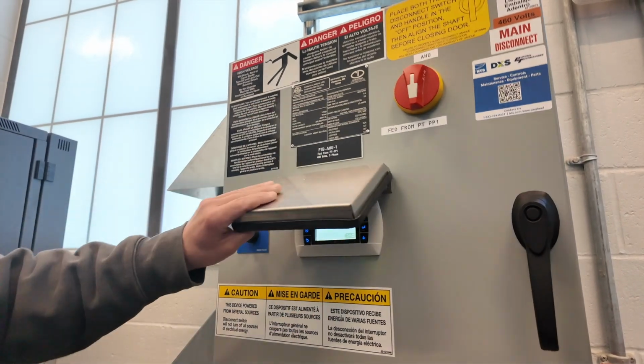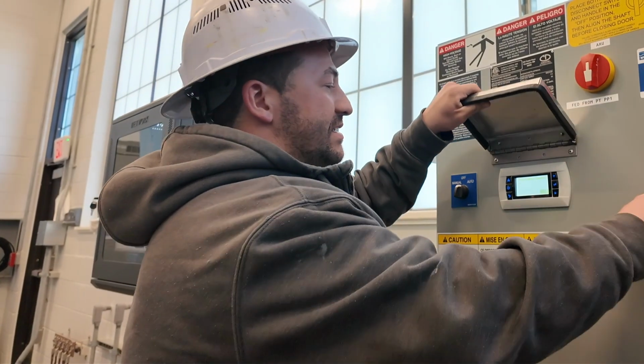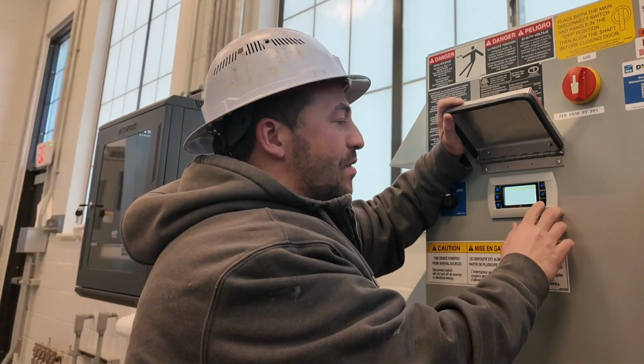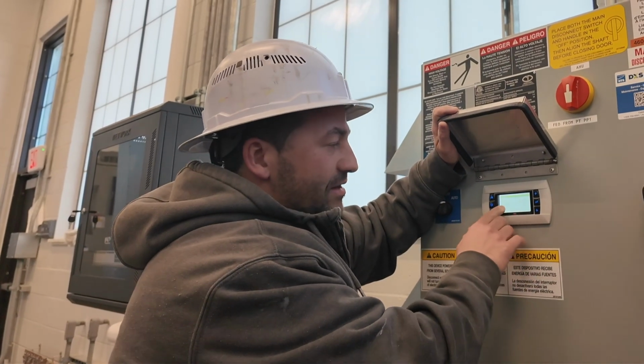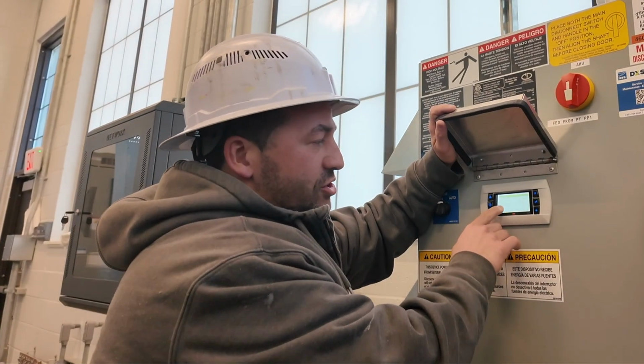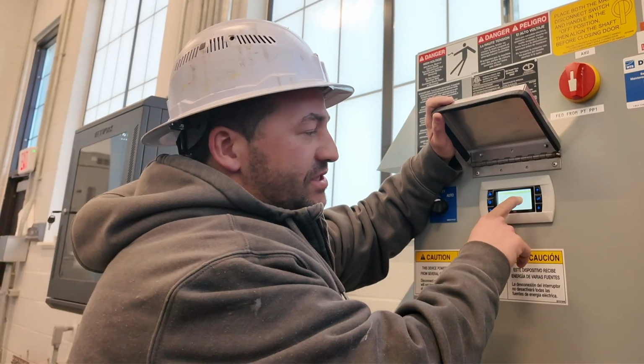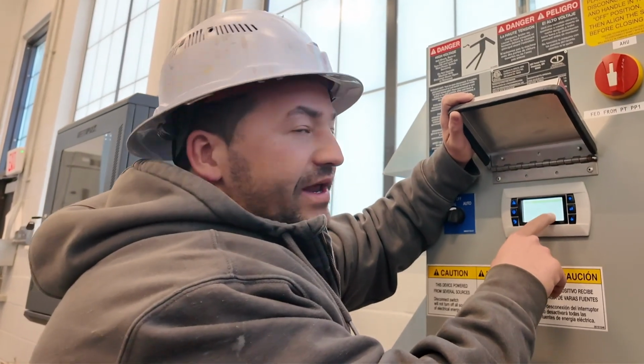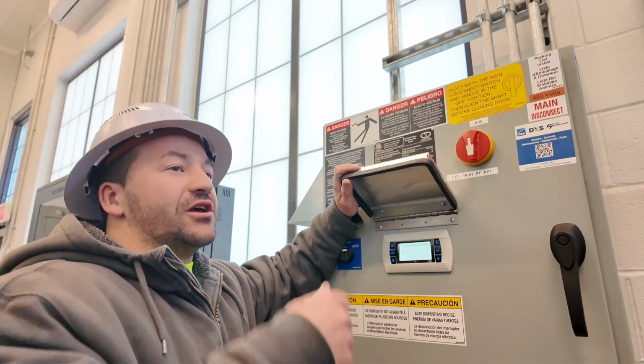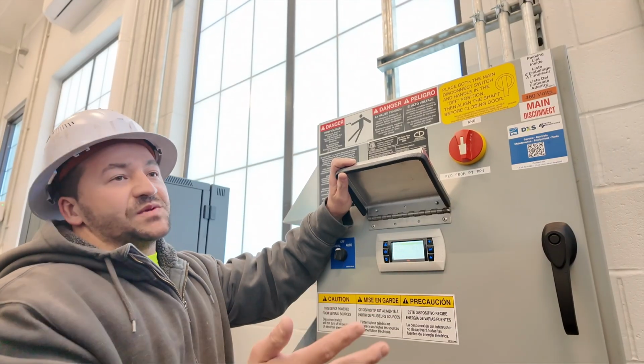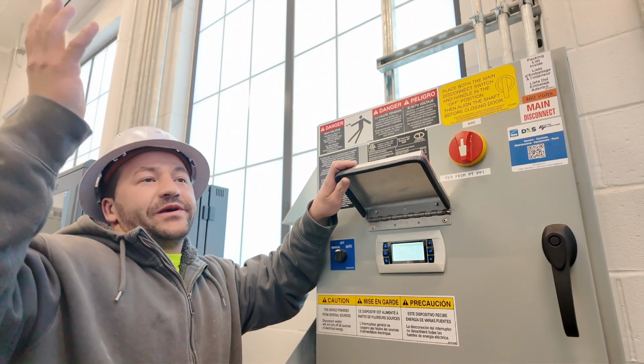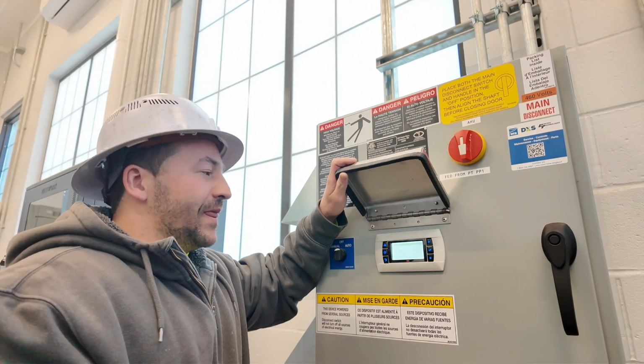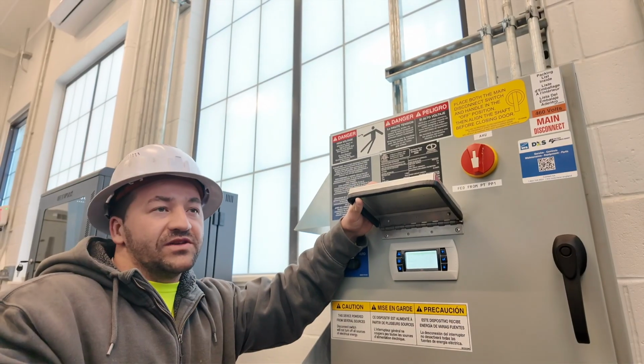So again, over there, if you need to see, for whatever reason, what percentage the valve is at, go to this page, and it'll show you what your temperature is currently, your set point, and how open the hot water valve is. Just look at the valve and say, all right, this valve is supposed to be 50% open, the valve's clearly closed, something's wrong. You know what I mean? Vice versa. I will move over to the actual unit.